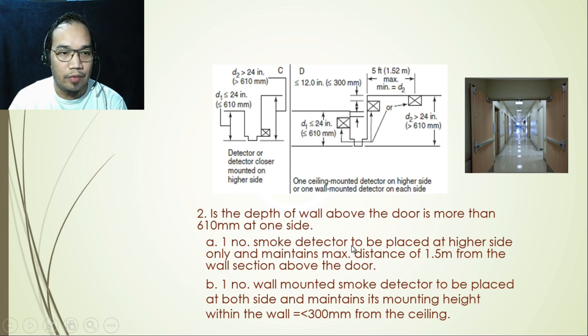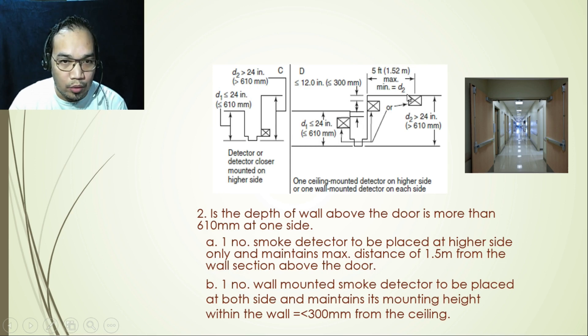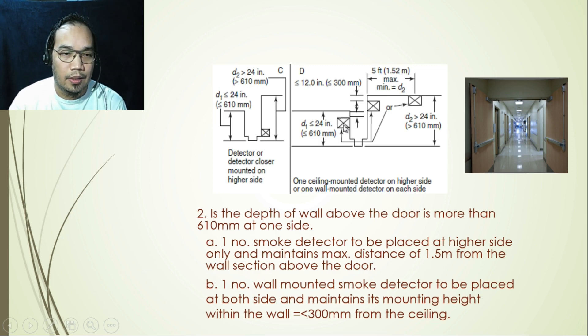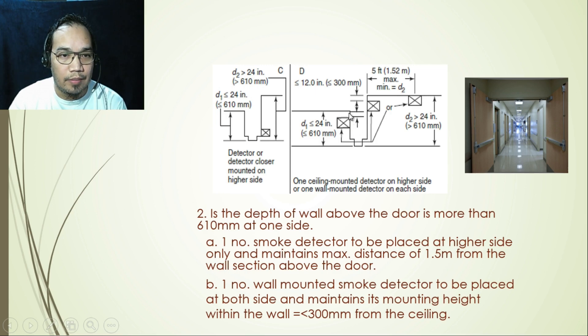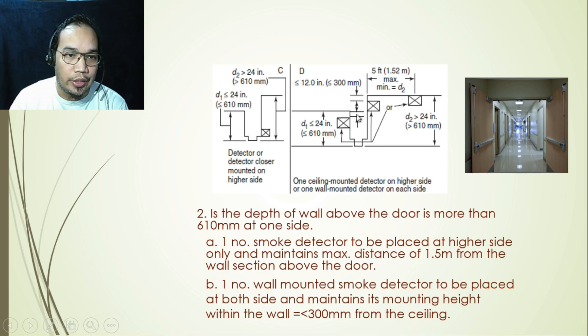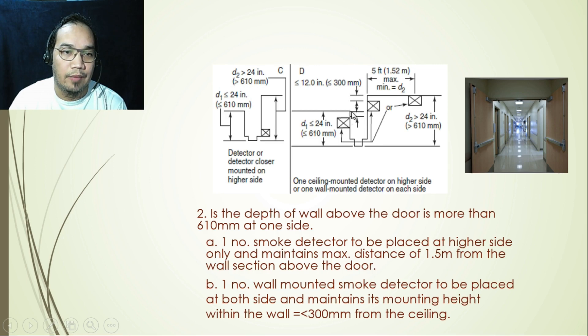When the wall depth is more than 610 mm on one side, the requirement is to either provide one smoke detector on the higher ceiling side, maintaining 1.5 meters distance from the wall above the door, or provide detectors at both sides of the door wall-mounted. For wall-mounted detectors, we need to maintain a mounting height of less than or equal to 300 mm from the ceiling.